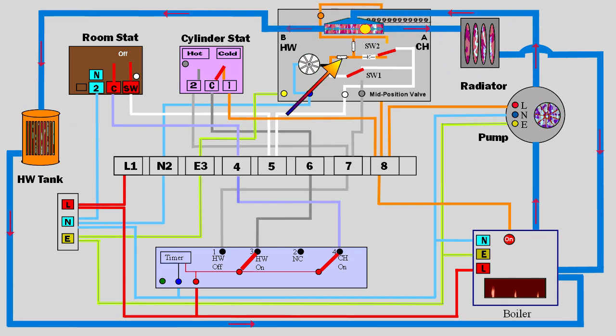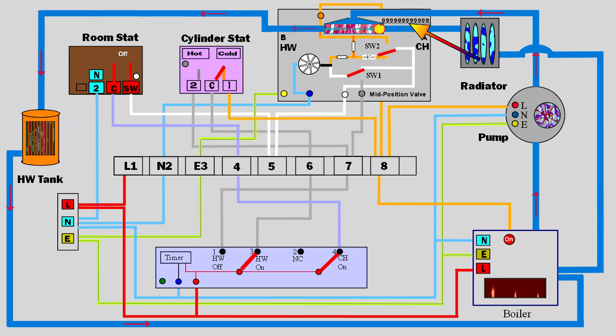The two resistors fed from orange remove any residue magnetic effect in the motor caused by the stalling effect, allowing the valve to move smoothly by the spring tension. The valve has returned to its default position and has closed port A, turning off the flow to the radiators.